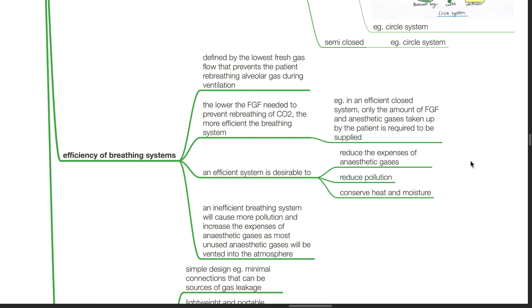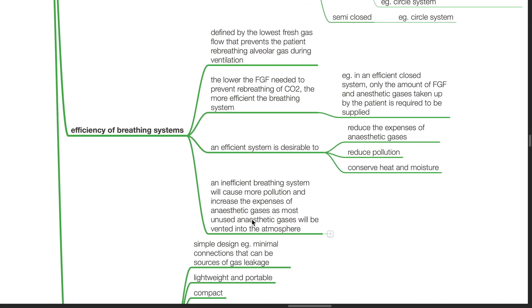For example, in an efficient closed system, only the amount of fresh gas flow and anesthetic gases taken up by the patient is required to be supplied. An efficient system is desirable to reduce the expenses of anesthetic gases, reduce pollution and conserve heat and moisture. An inefficient breathing system will cause more pollution and increase the expenses of anesthetic gases as most unused anesthetic gases will be vented into the atmosphere.